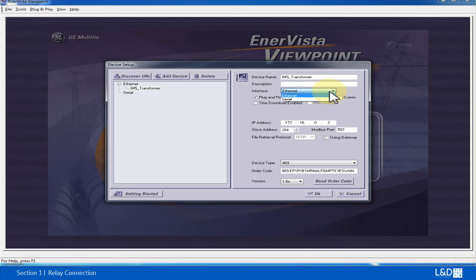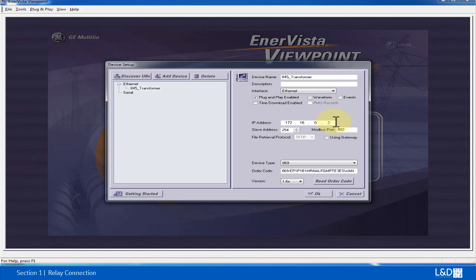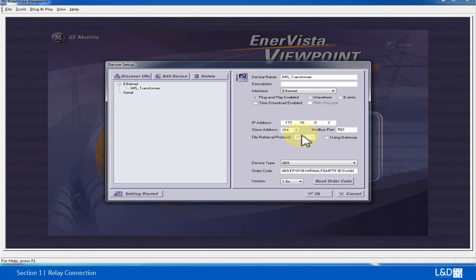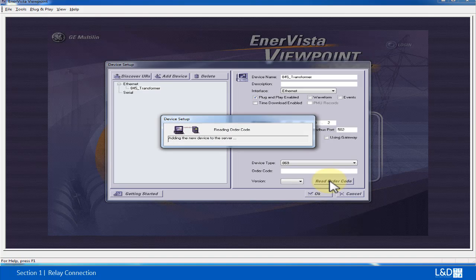For interface, we have only Ethernet and Serial port, there's no USB. So even if our USB is connected with the relay, we still choose Ethernet port and we use the IP address of the USB connection 172.16.0.2 as the IP address. Use the same slave address and Modbus port address as we showed in the USB connection, and then we can click read order code.